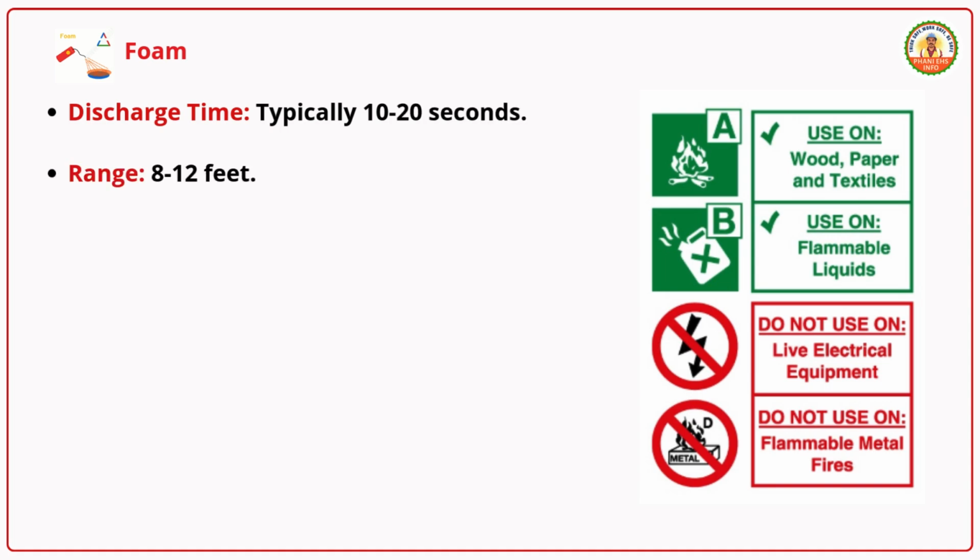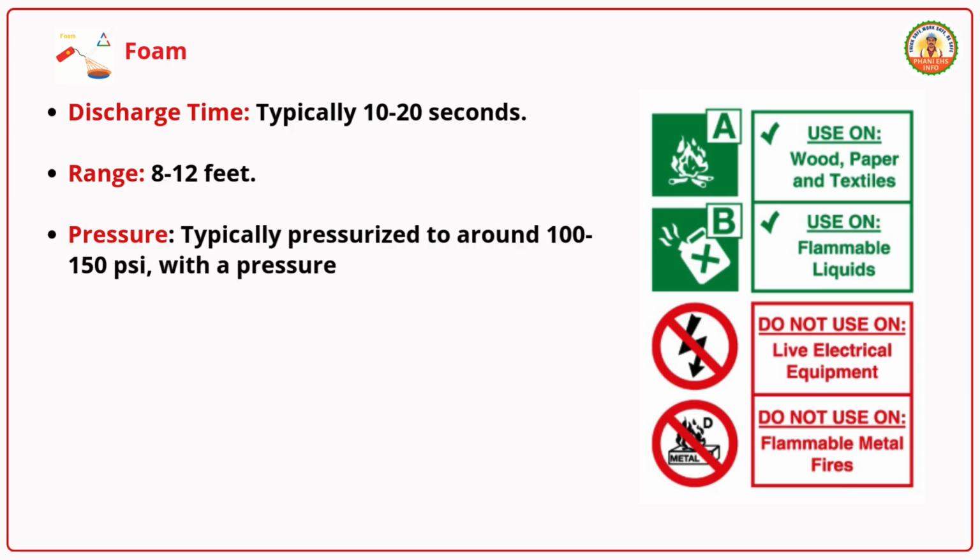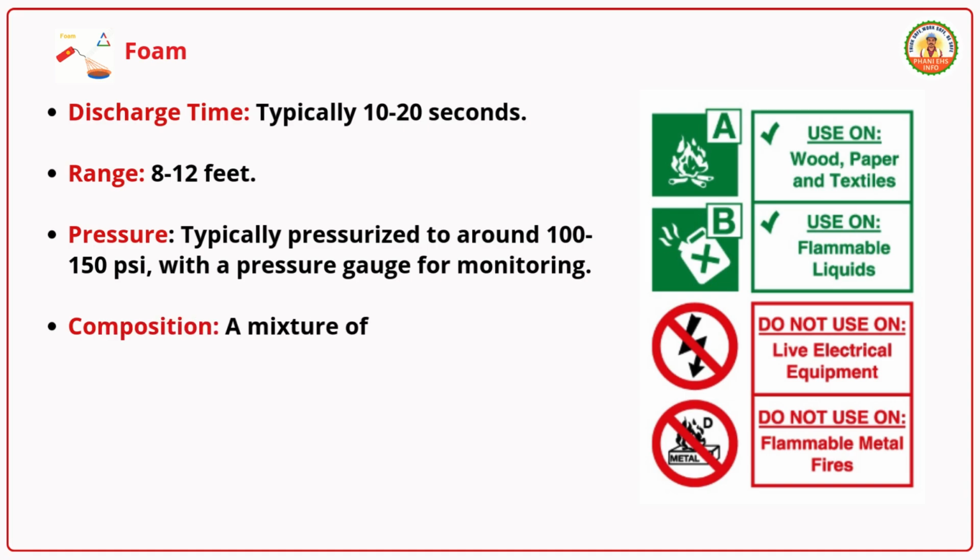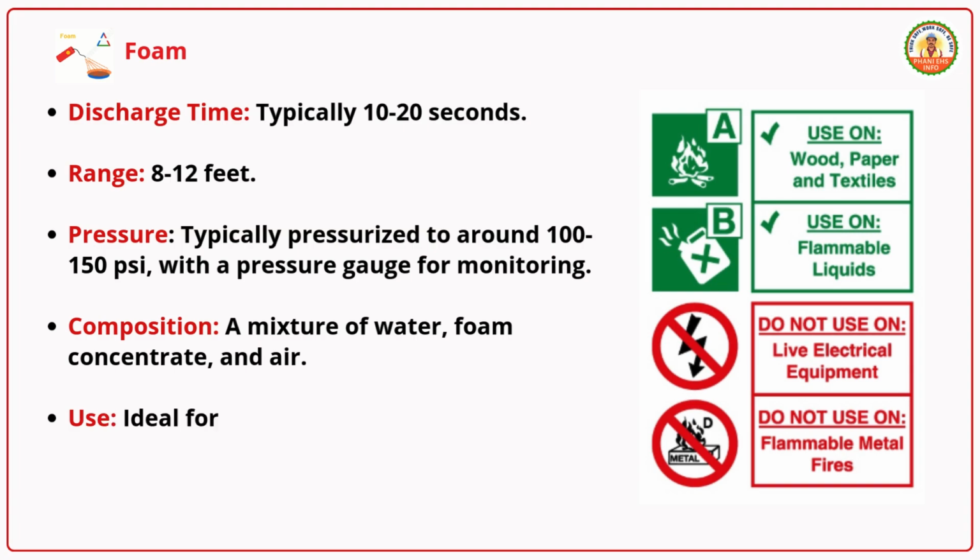Foam. Discharge time: typically 10 to 20 seconds. Range: 8 to 12 feet. Pressure: typically pressurized to around 100 to 150 psi, with a pressure gauge for monitoring. Composition: a mixture of water, foam concentrate, and air.